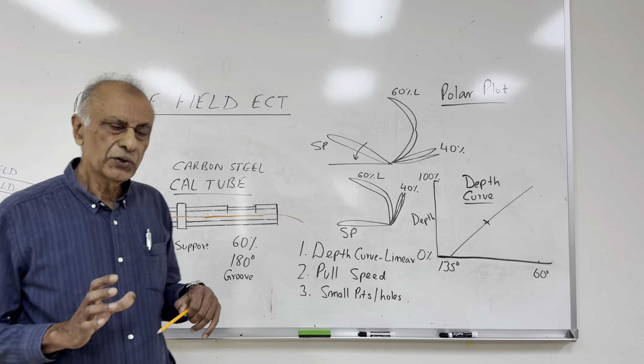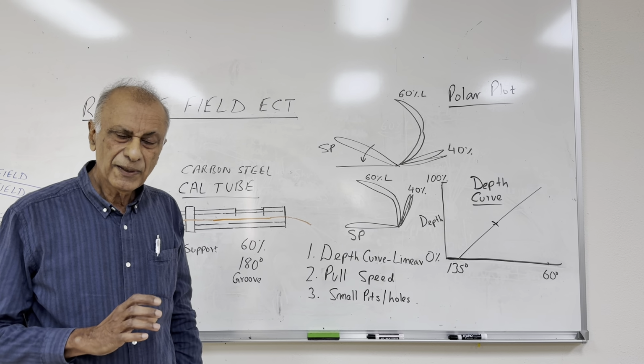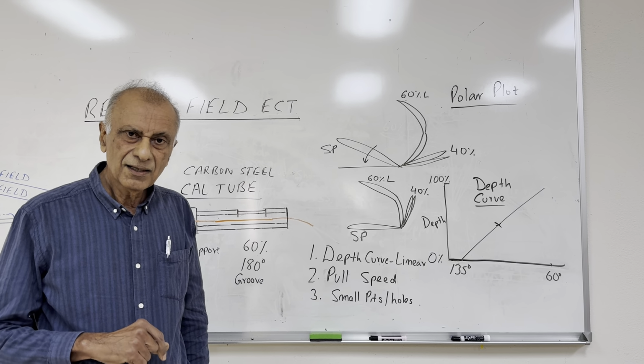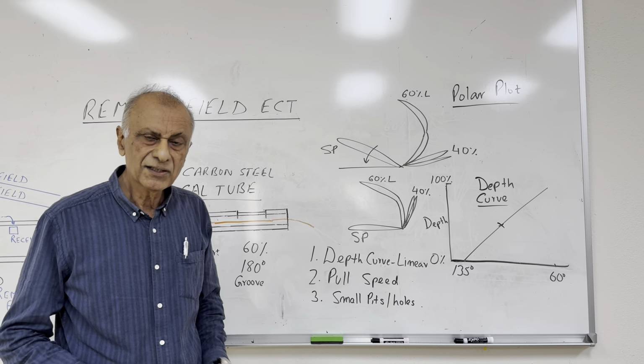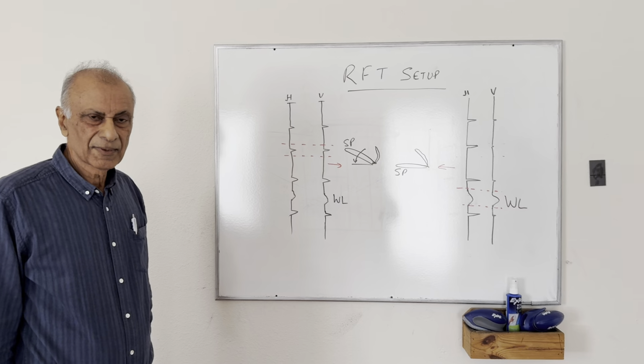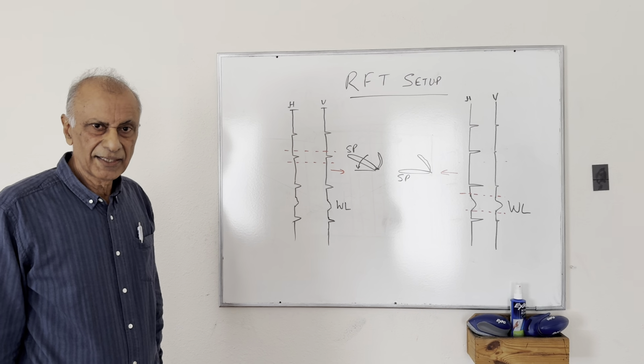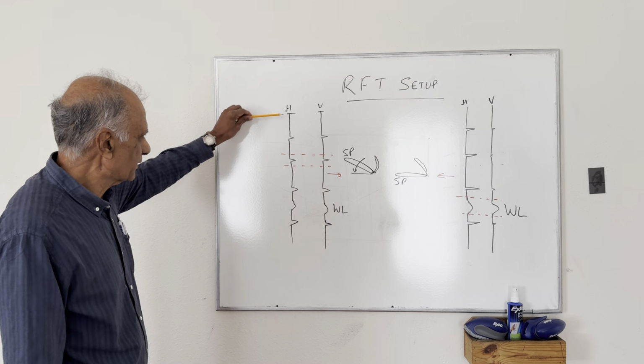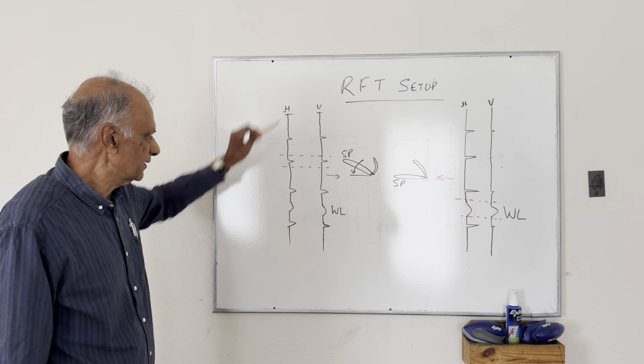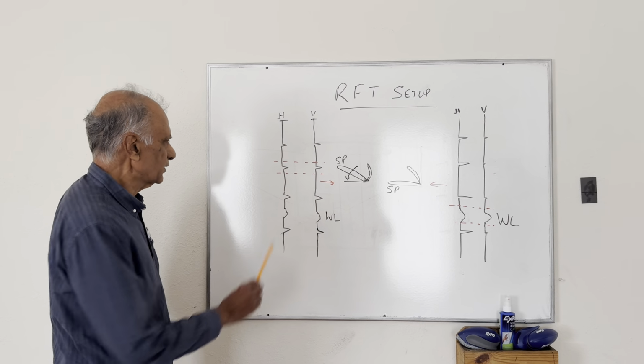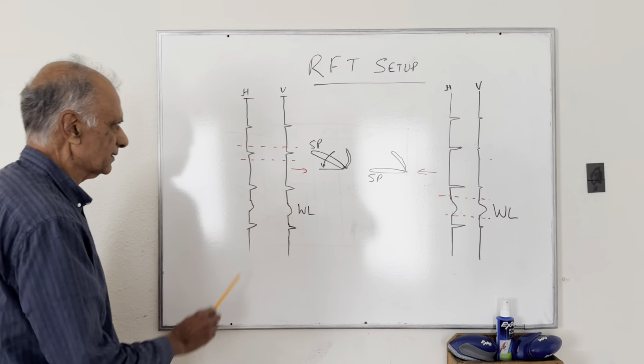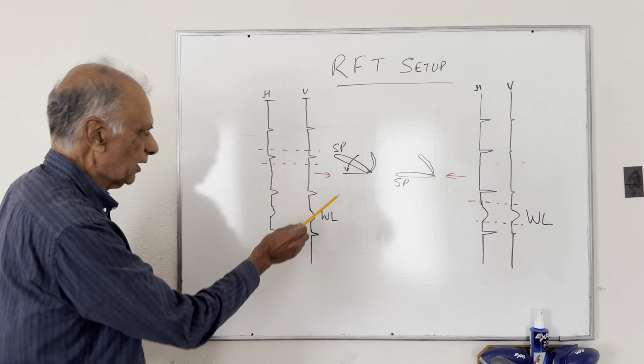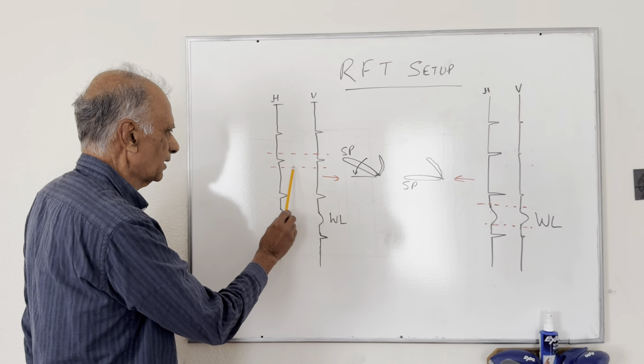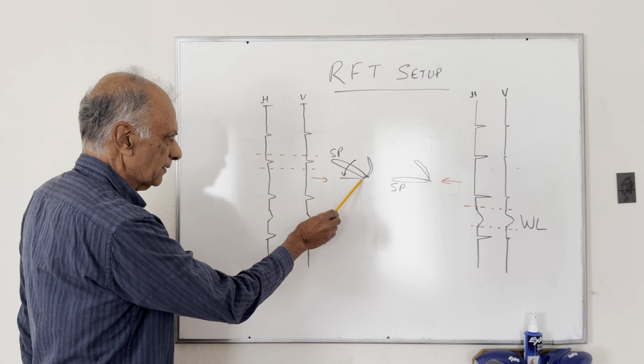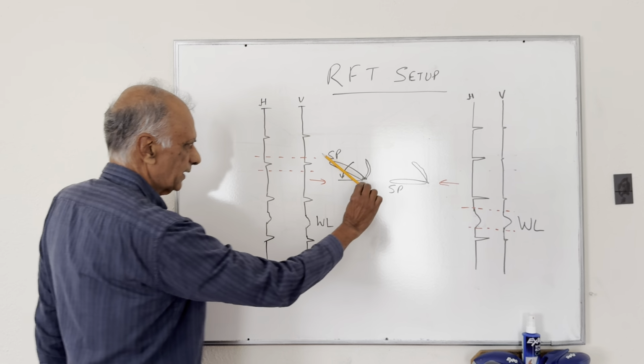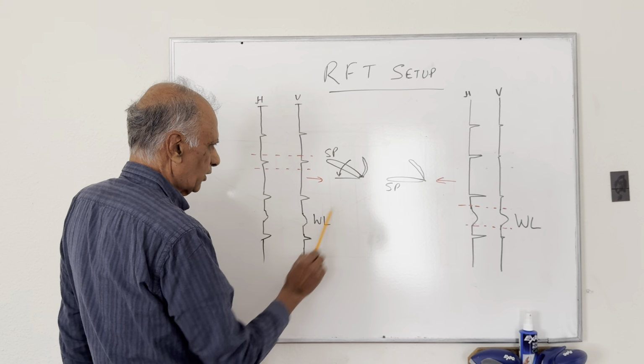So now I will show you the next step when you do the inspection, how you reset the phase for the actual inspection in a heat exchanger tube. Okay. So now we start the inspection in a heat exchanger tube, and this is what it's going to look like. This is a horizontal strip chart, vertical strip chart, and what you would see initially is the support plate signals here. We have 4 support plates, and then you look at the polar plot and you get one of the support plates here. This is number 2, and then you look at the polar plot and you will see the support plate, let's say, going at this angle, and this is the wall loss signal, which is right here.